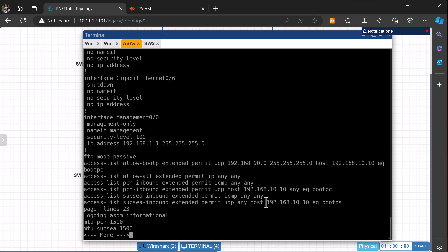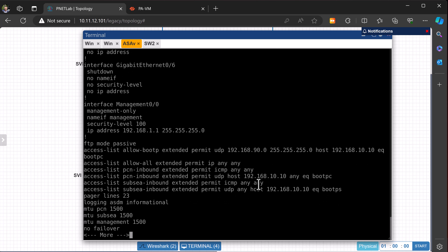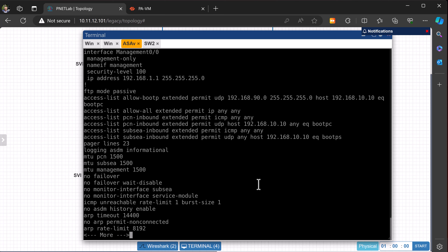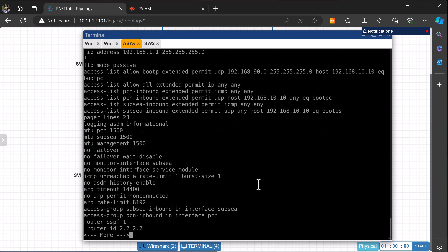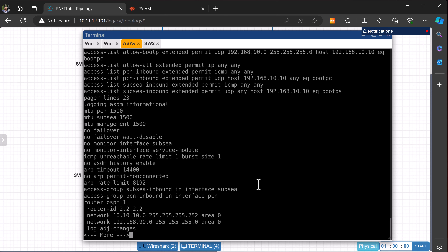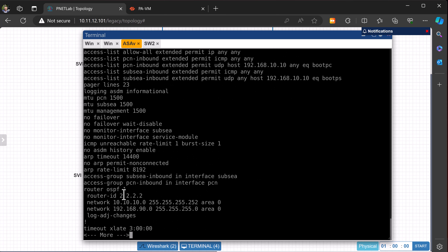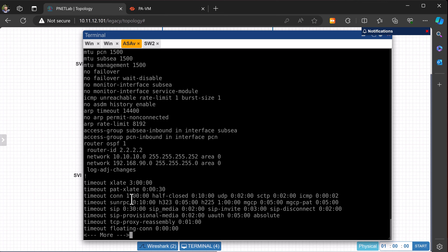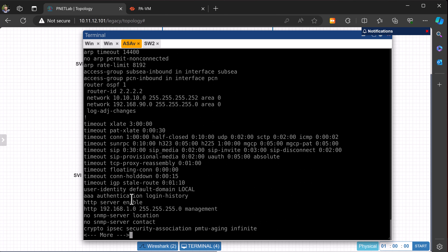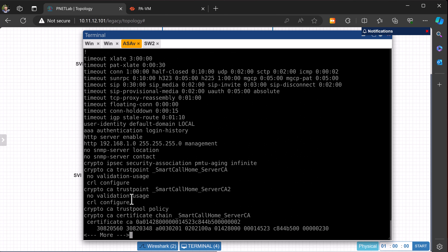It's been named subsea and given a security level, so the other interface cannot connect to it. The only other interesting thing in here is the access list. You've got a couple of access lists in here which are not actually configured — we're just using them for testing. But there's an important one: PCN inbound, which basically allows any ping from anywhere to anywhere.